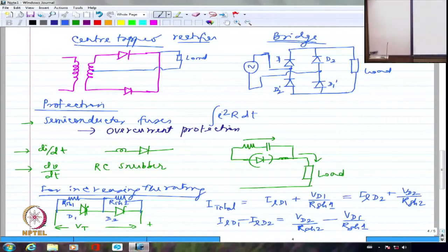Whenever we talk about high power drives, especially motor drives, almost 50 to 60% of the processor time goes towards protection. Rest of 30-40% only really goes towards control of the devices. 50 to 60% is going towards protection means we are really worried about the life of each of these devices, because each of the devices can cost crores of rupees. That is the reason we'll have to be extremely careful about the devices. So we would definitely characterize each of them normally, especially when we talk about very, very high power applications.